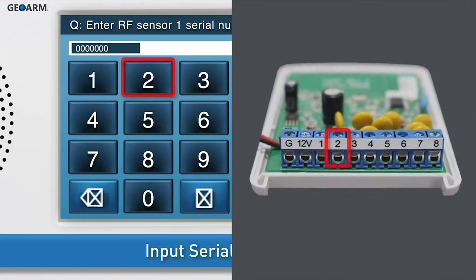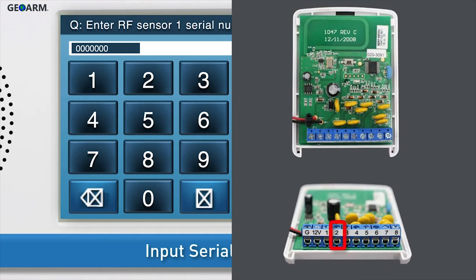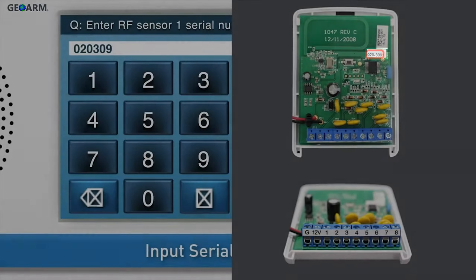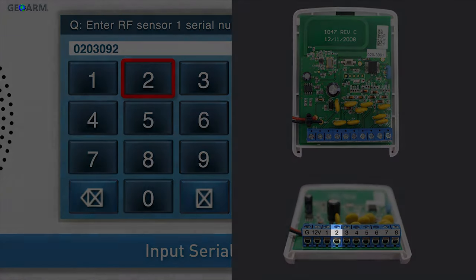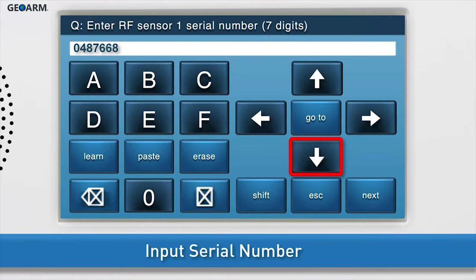Then, type the input number you are currently programming. In this example, we are programming input 2 on the takeover module, so we will type 0, 2, 0, 3, 0, 9, which are the first six digits of the serial number, and then 2, which is the input number. Press the down arrow to go to the next sub-question.